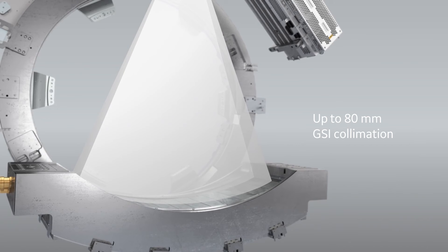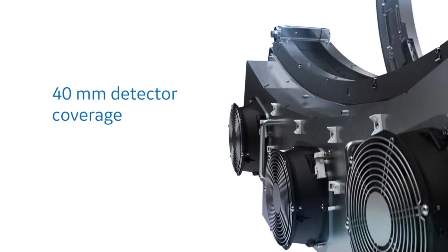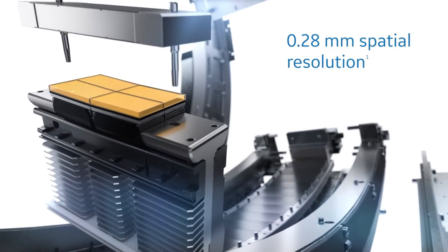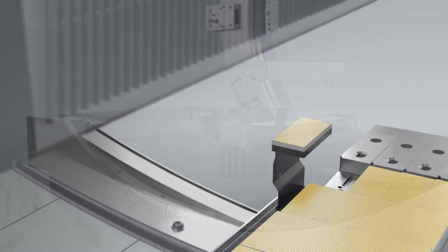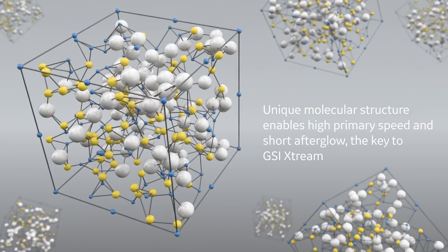The last component is the detectors. Detectors collect information regarding the degree to which each anatomic structure attenuated the beam. In conventional radiography, a film-screen system records attenuated information, whereas in CT, detectors are used. The detector array describes the entire collection of detectors in the system, comprising detector elements situated in an arc or ring, each measuring the intensity of transmitted X-ray radiation along a beam projected from the X-ray source to that particular element. Also included are reference detectors that help calibrate data and reduce artifacts. Detectors can be made from different substances, each with their own advantages and disadvantages.